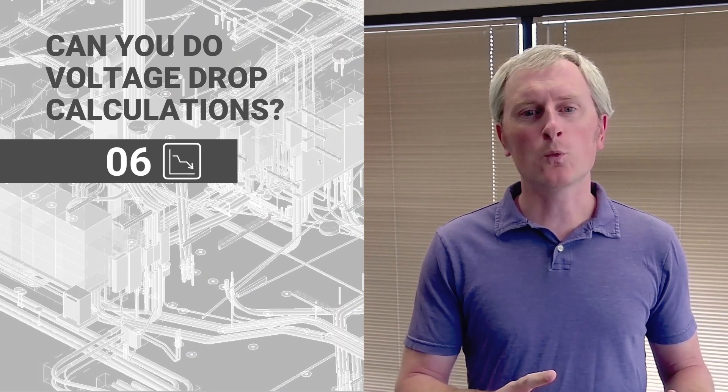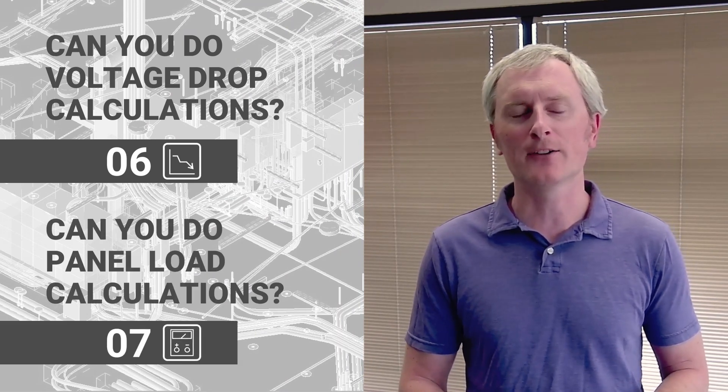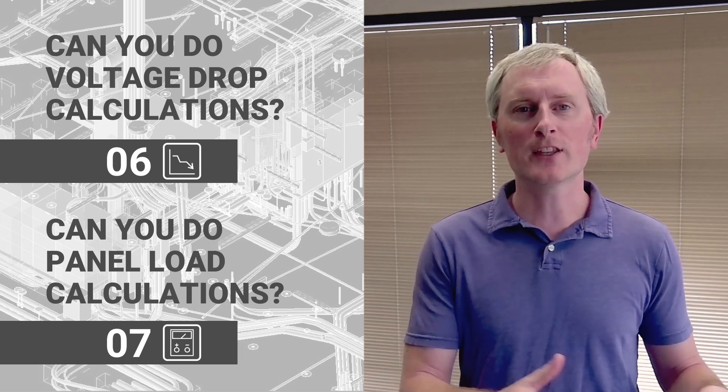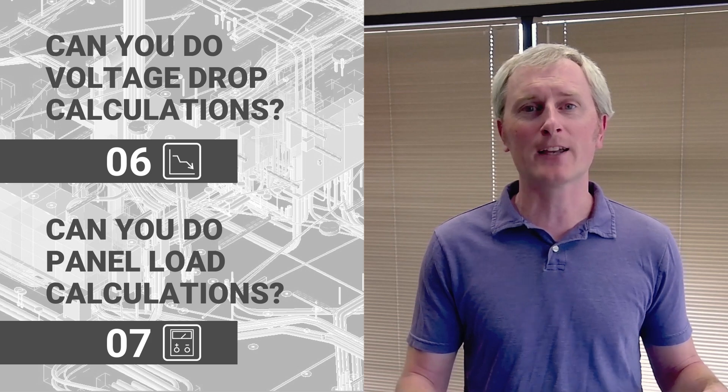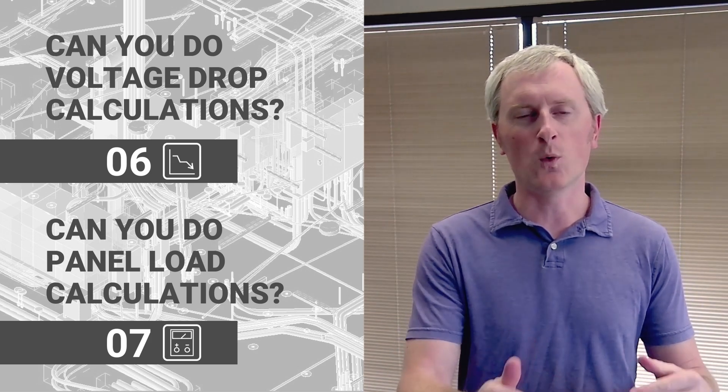The next two questions are whether you can do a voltage drop calculation and whether you can do a panel load calculation — a score of six or seven. Six if it can do one, seven if it can do both. Voltage drop is the first obvious calculation: you have your devices laid out, you have wire sizes, and you can pull wire lengths from the model. Then panel load calculations look at feeder and service load calculations, applying demand factors to figure out what the actual load on a panel is going to be.